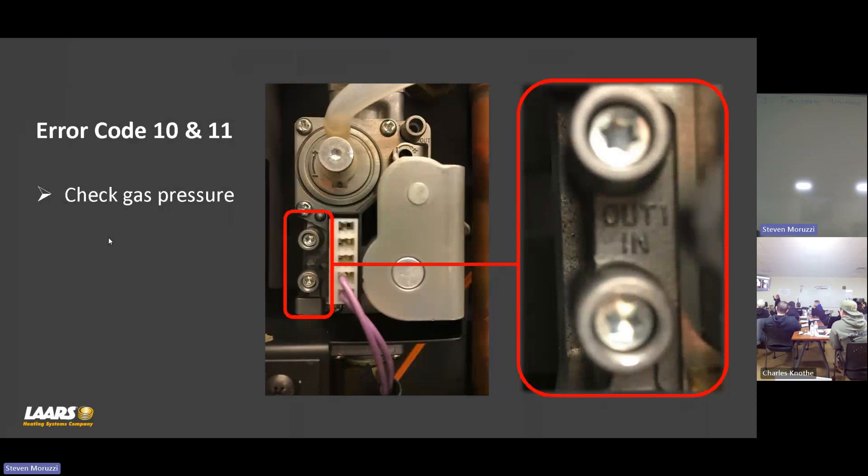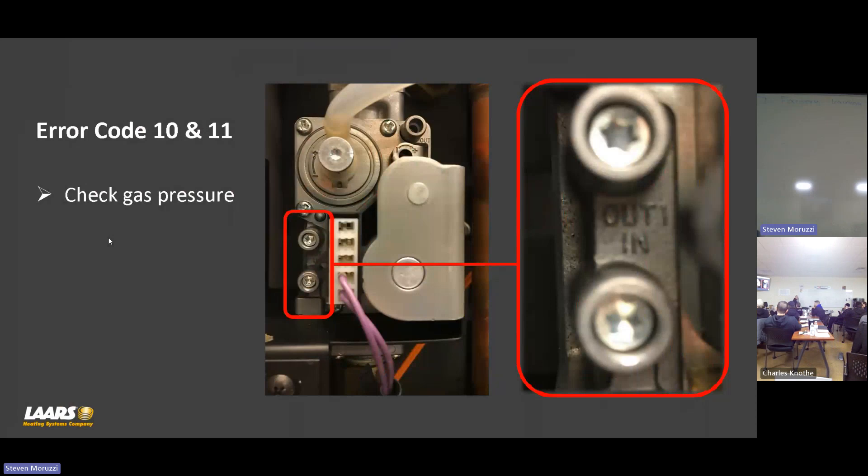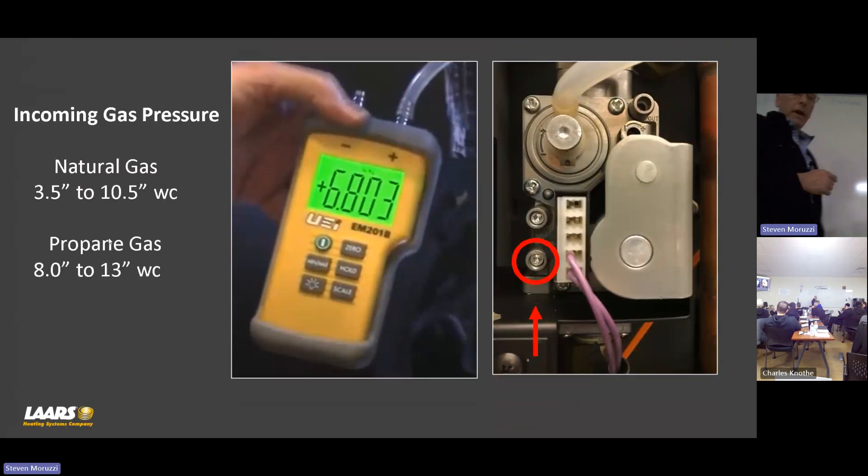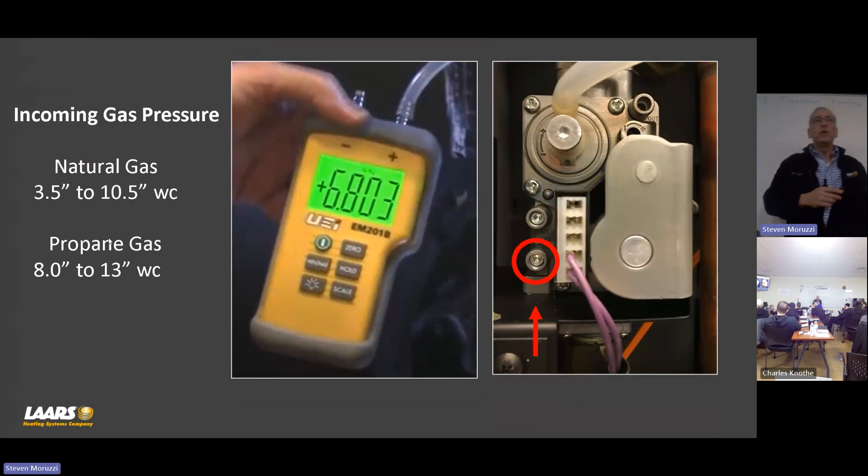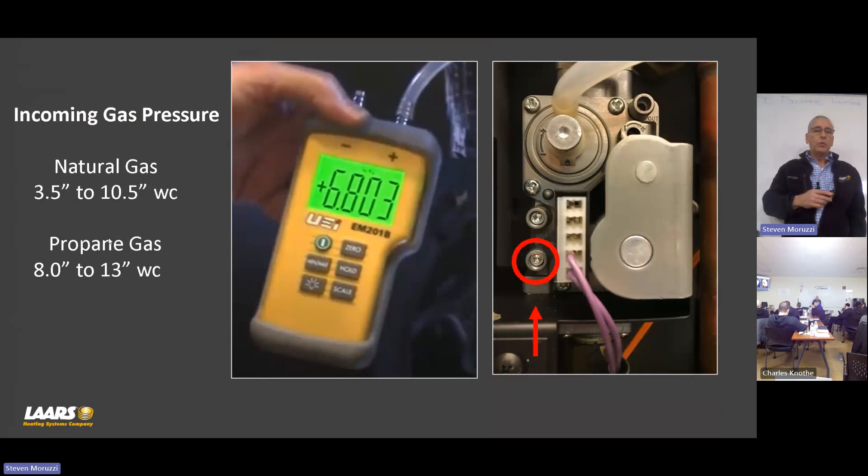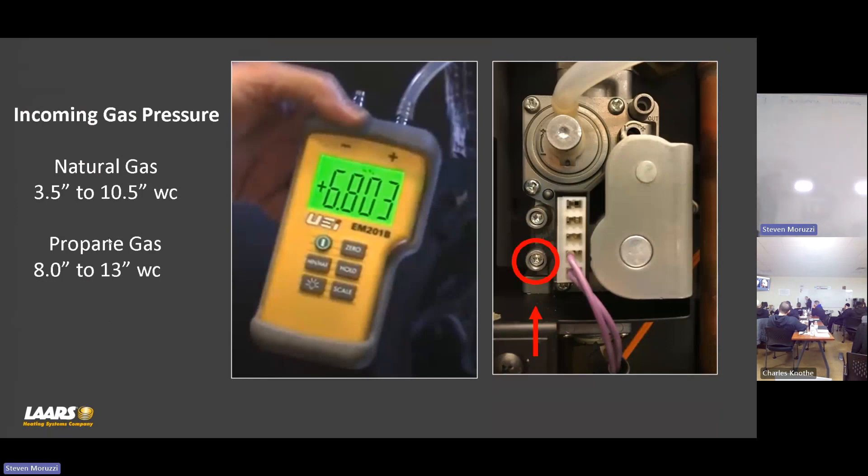So gas pressure. We want to put a manometer on that. You're going to have it read in and out or downstream or manifold. Outlet pressure would be the out on that. First thing to check for is fuel input. Our range for natural gas is three and a half to ten and a half. On propane is eight to 13. What did I ask? What did I say to you guys our minimum, our max pressure drop can be? One full inch.